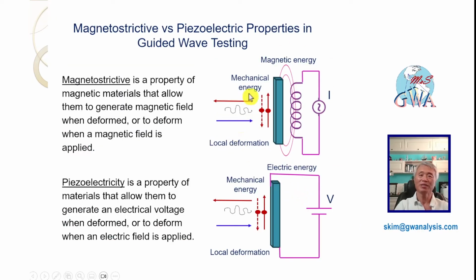This is a schematic drawing of magnetostrictive and piezoelectric properties of material that are used for guided wave testing. First, magnetostrictive properties. The magnetostrictive materials, typically ferromagnetics, exhibit the property of generating magnetic field when they undergo mechanical deformations. Conversely, they are also deformed when exposed to an external magnetic field. This property is utilized in the magnetostrictive sensor MSS for generating and detecting guided waves in structures. Second, piezoelectric properties. Piezoelectric materials such as quartz or ceramics generate electric voltage when deformed mechanically. Similarly, these materials deform when subject to an electric field. This characteristic is key in the piezoelectric transducers for generating and detecting ultrasonic and guided waves.